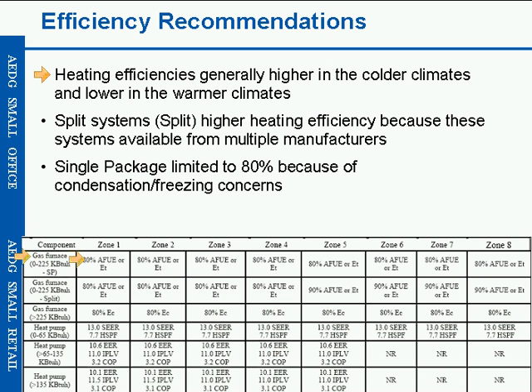there's concern when you have a system that's outside and freezing with the condensation. So 80% is the maximum that was available from multiple manufacturers on the heating efficiency for some of the furnace systems. For the split system, there are higher efficiencies available, and those are recommended in the colder climate zones, climate zones 5 through 8, and you'll see that in the split system recommendations for the small office and small retail design guide. And finally, the heat pump recommendations are shown for climate zones 1 through 8, based on EER and COP on the heating side.